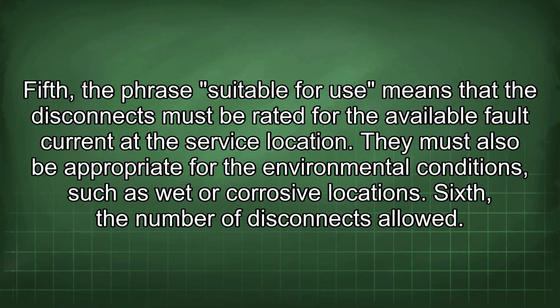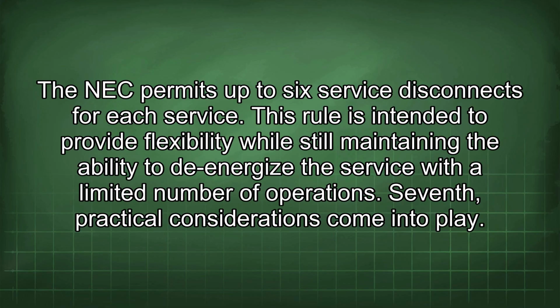Sixth, the number of disconnects allowed. The NEC permits up to 6 service disconnects for each service. This rule is intended to provide flexibility while still maintaining the ability to de-energize the service with a limited number of operations. Seventh, practical considerations come into play.